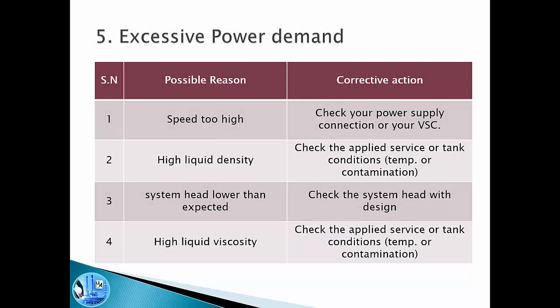The last problem is excessive power demand. One possible reason is that the pump is running at very high speed — we need to check the power supply connections or the variable speed controller to ensure it is running as designed. Another reason could be high liquid density — we need to check the service conditions or tank conditions. Maybe the tank heater is not working, there is contamination from another liquid affecting the total liquid density, or we are using this pump for a different liquid than what it was designed for, such as pumping water instead of oil when the pump was designed for oil.